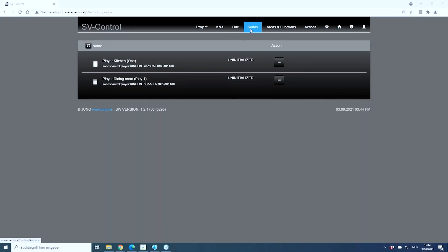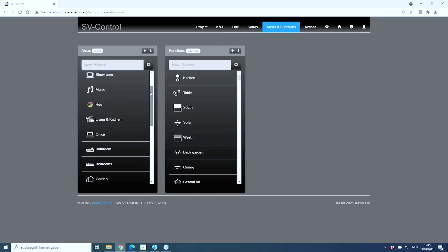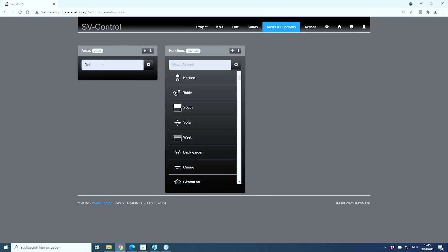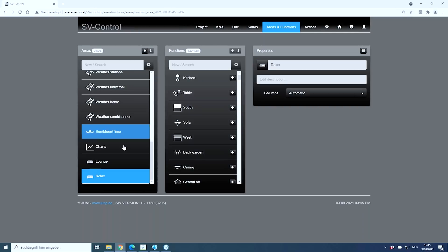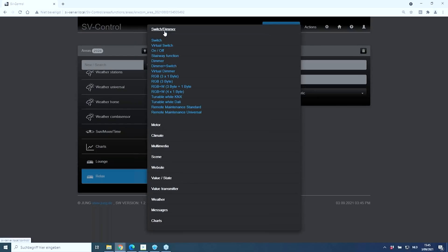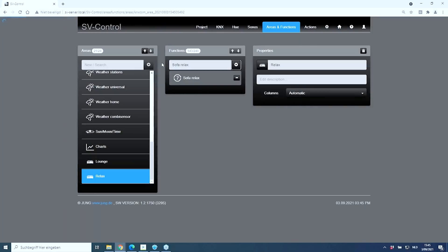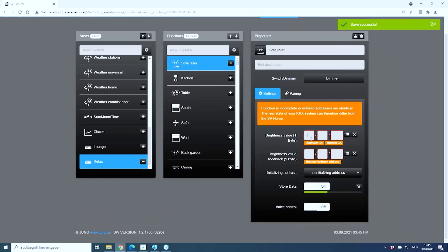Once those three steps are done, we proceed with areas and functions. It's very easy — first we create areas. I have already prepared some, and I'll create a new one called 'Relax', assigning a corresponding symbol that will be visible in the visualization. To this area I can now assign new functions. For 'Relax' I define the function type — in this case, a dimmable light — and select a corresponding symbol. We then need to connect the group addresses.